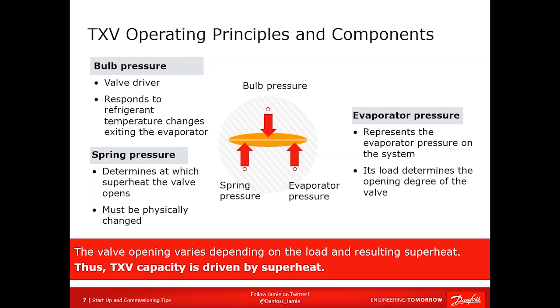Most systems have a TXV today. It wasn't that way in 2007, but when SEER 13 came in, the whole market changed towards adaptive metering devices, mechanical adaptive metering devices, TXVs. And the TXV operates by a balance of forces. You have one opening force, and that's your bulb pressure. The other two are closing forces. The only time that TXV is going to open up is when that bulb pressure exceeds the force provided by the spring and evaporator pressure. And they're both forcing onto either side of that diaphragm.